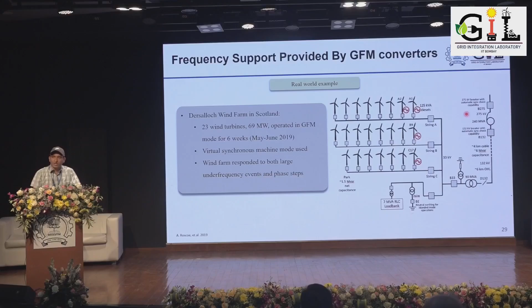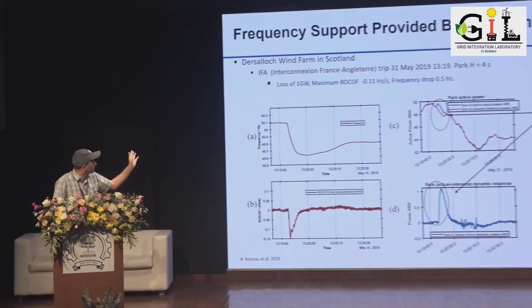Every time we introduce new technology in the system, there are new challenges that come along with it. If you look at the next slide, this shows how this grid forming based wind power plant is actually supporting the grid in terms of inertia and other aspects. This is a field demonstration of the same, where because of this tie line tripping, the plant is actually providing the inertial support or fast frequency support to the grid because of the grid forming technology implemented in this wind power plant.